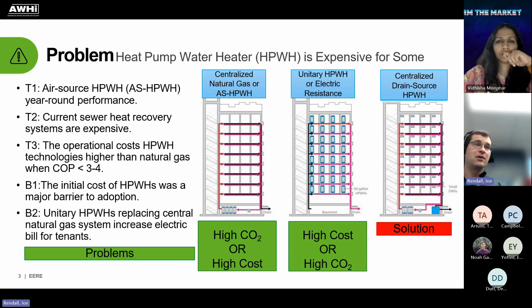So we came up with something called the centralized drain source heat pump water heater. You'll see little distributed tanks in this figure, but those ended up being too expensive once we did the cost analysis of the distributed portion. Any tank you put everywhere has to be maintained. One key factor in the financials is that a unitary heat pump water heater needs replacing after about 15 years, whereas a centralized system can last closer to 30 years—there's a pretty big cost disparity when you do a life cycle cost analysis.